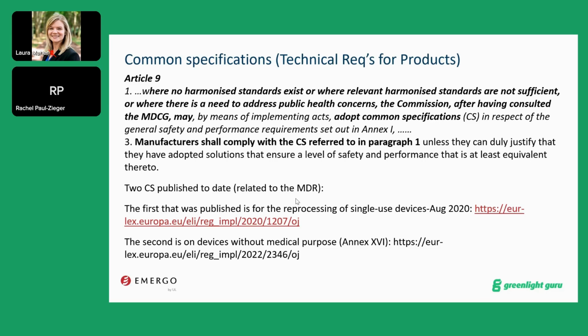Today, at this date, there are only 2 common specifications published. The first one was about the reprocessing of single-use devices. And the second one is about devices without medical purpose. But it is expected that more common specifications will be developed. So, for example, if you are a manufacturer of dermal filler, the common specification on devices without medical purpose is applicable for you, and you need to follow the requirements from this common specification.